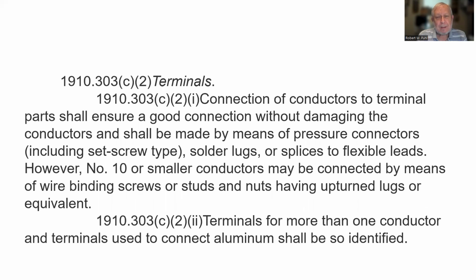Makes sense. Terminals: connection of conductors to terminal parts shall ensure a good connection without damaging the conductors and shall be made by means of pressure connectors, including set screw type, solder lugs, or splices to flexible leads. However, number 10 or smaller conductors may be connected by means of wire binding screws or studs and nuts having upturned lugs or equivalent. Terminals for more than one conductor and terminals used to connect aluminum shall be so identified.